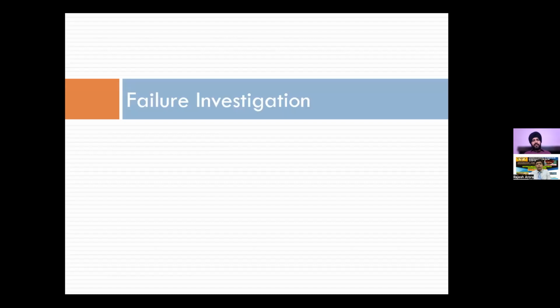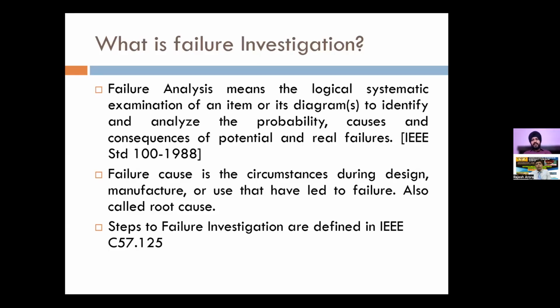Now, when we talk about failure investigation, first of all, if there is any tripping or any other incident, how does the transformer need to be investigated? First we need to look at the definition of failure investigation as per IEEE C57.125. It defines the steps to investigate the failure. But first of all, we need to realize what failure analysis is.